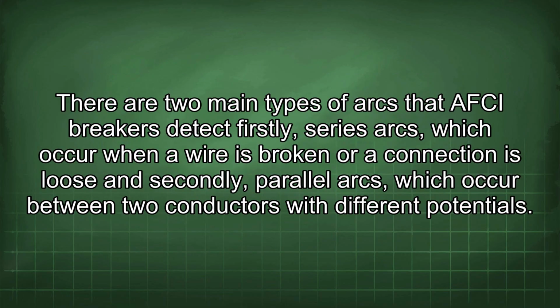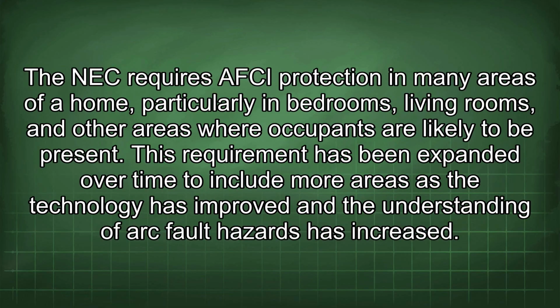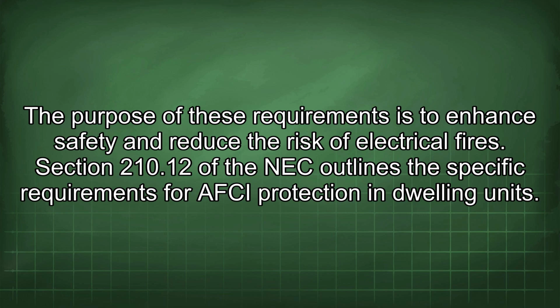There are two main types of arcs that AFCI breakers detect. Firstly, series arcs, which occur when a wire is broken or a connection is loose, and secondly, parallel arcs, which occur between two conductors with different potentials. The NEC requires AFCI protection in many areas of a home, particularly in bedrooms, living rooms, and other areas where occupants are likely to be present. This requirement has been expanded over time to include more areas as the technology has improved and the understanding of arc fault hazards has increased. The purpose of these requirements is to enhance safety and reduce the risk of electrical fires.